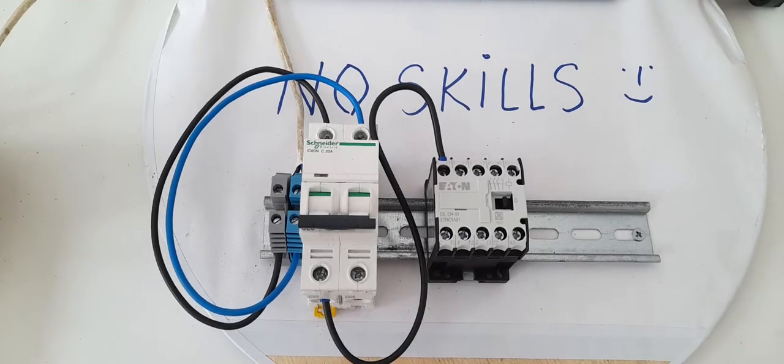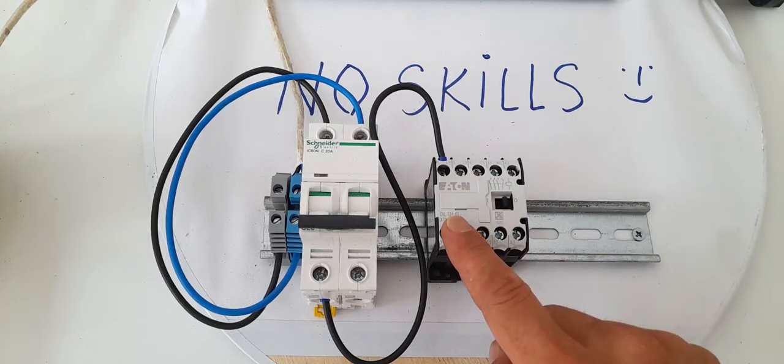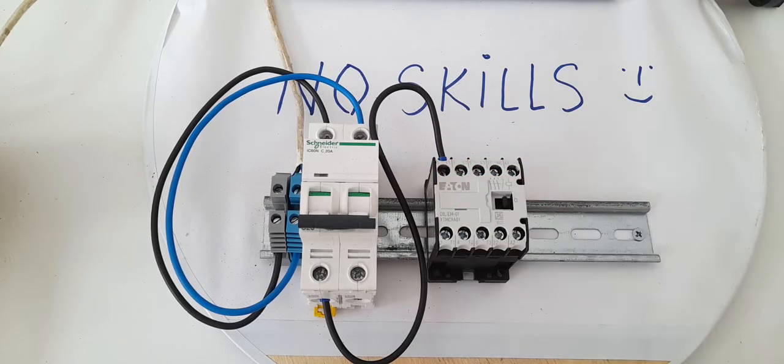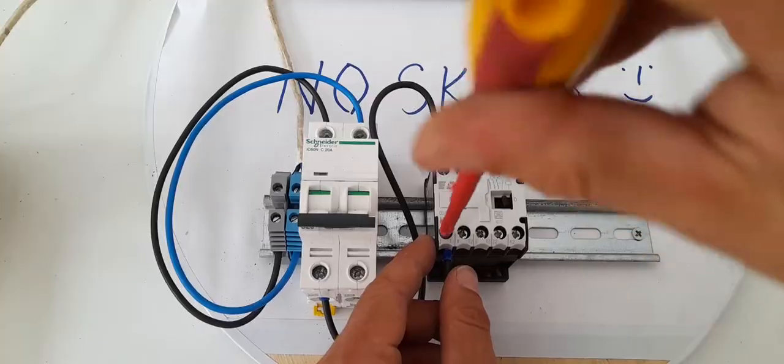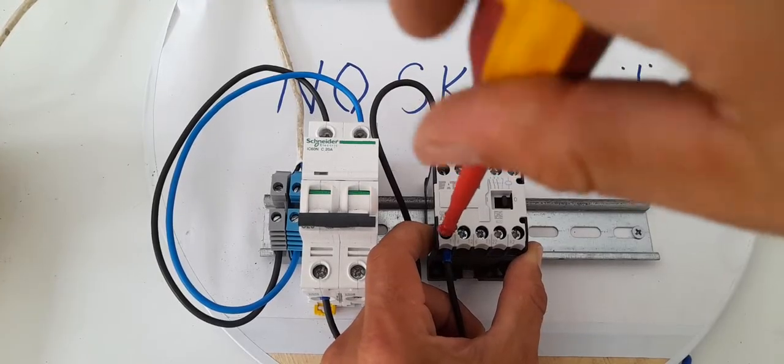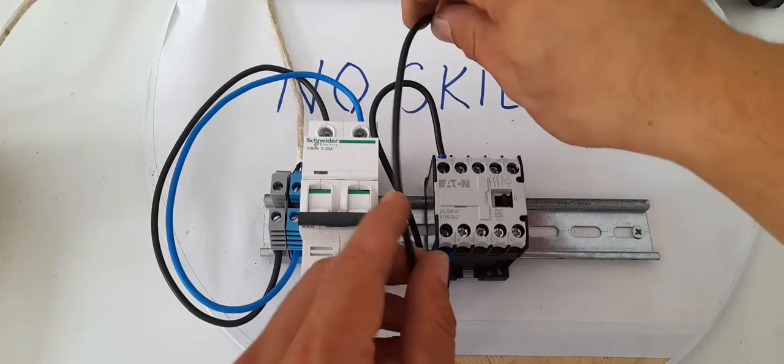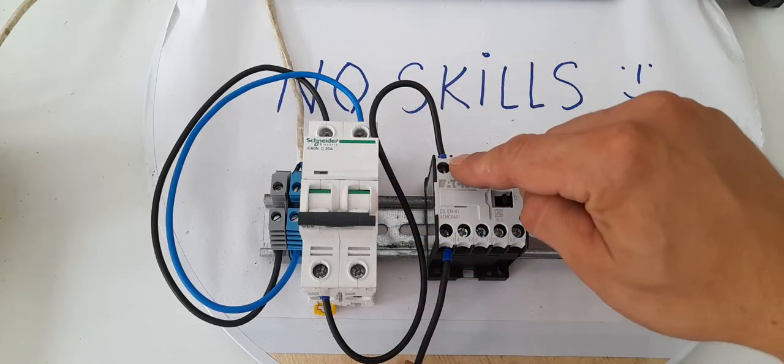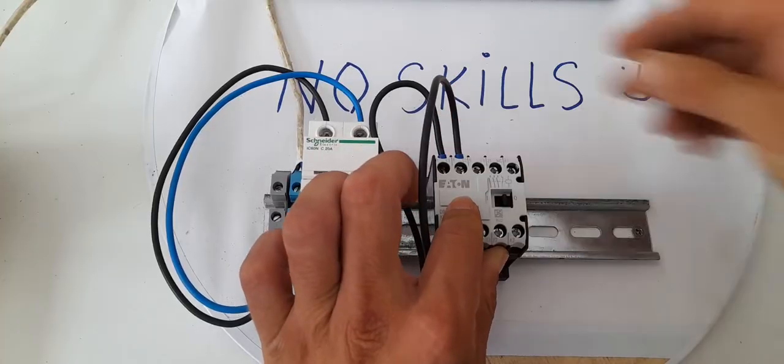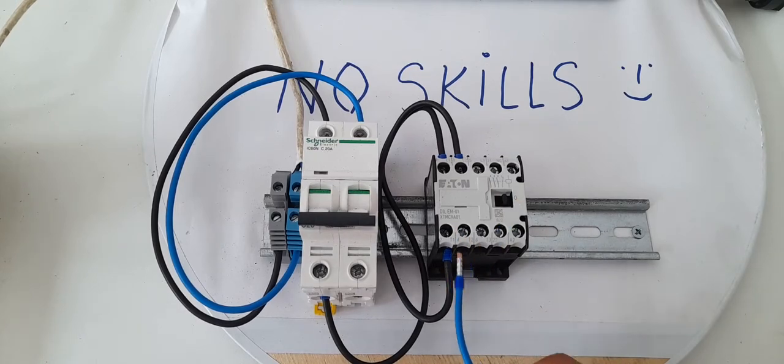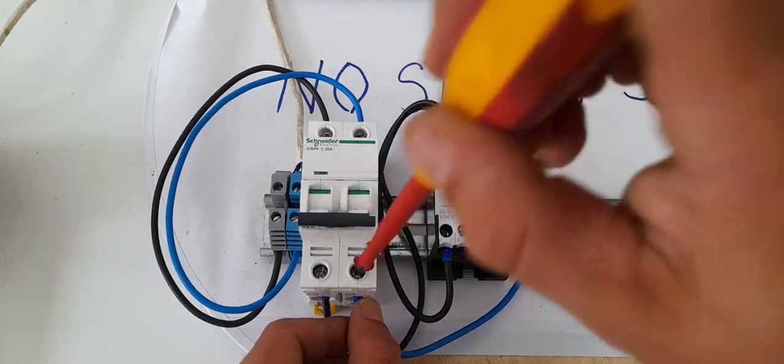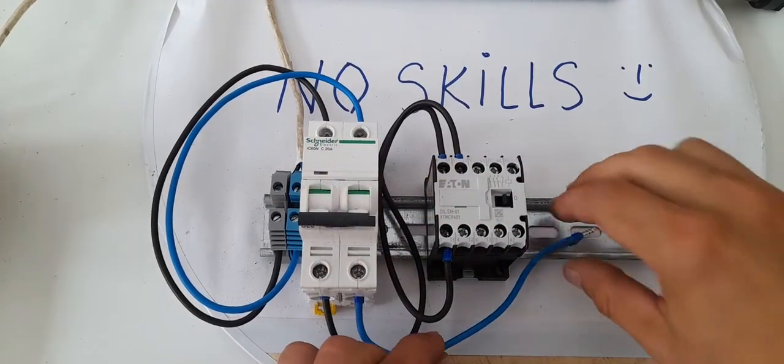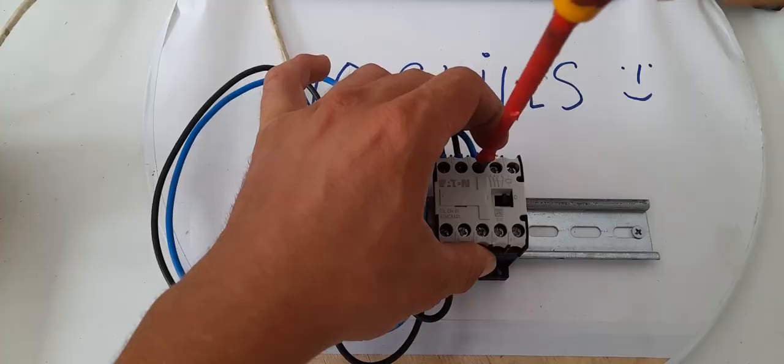Alright and then, this is a single phase and this is for all electricians now. We have put the mains, the line, live or whatever here. I'm gonna take a cable from the T1 and it's this method is called doubling up the contact. Basically the exit of this one I'm gonna put it back to the L2 so the live is coming in, it exits here and it's coming back to the L2 as well. So I have doubled up the contact, we got extra protection as well.